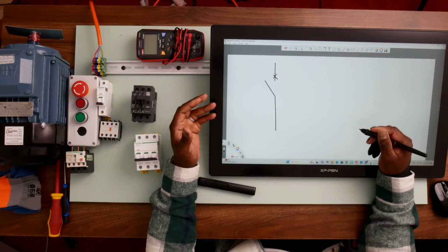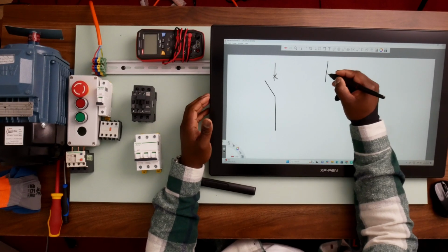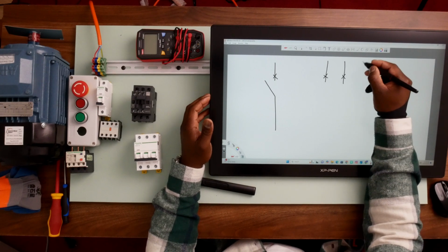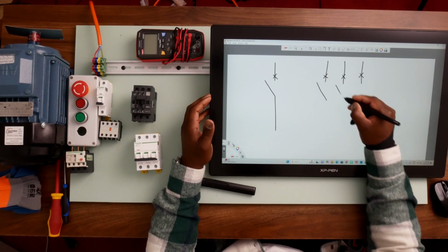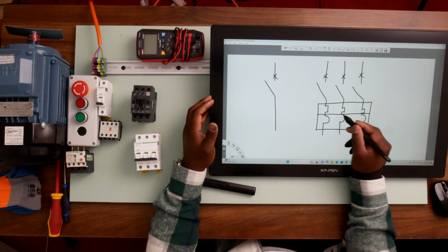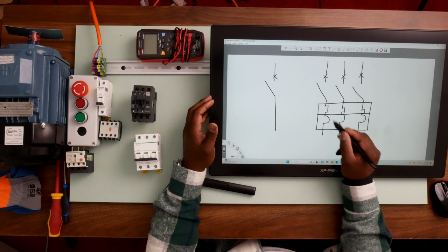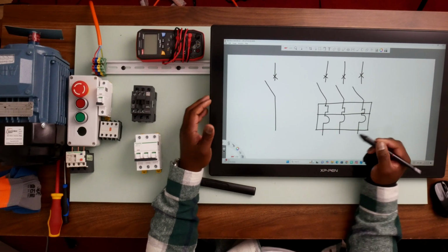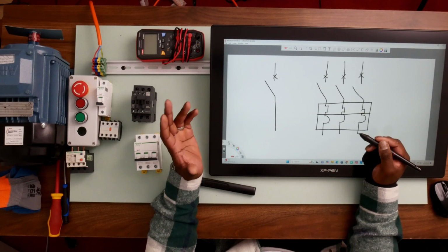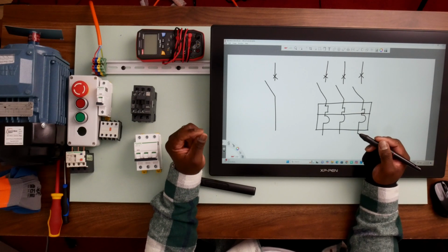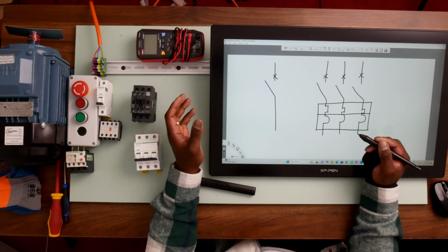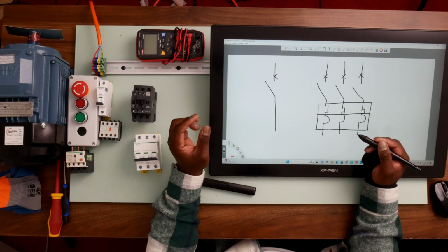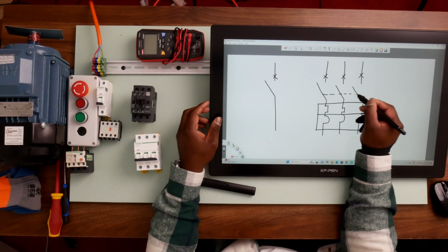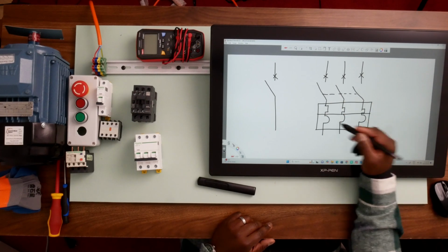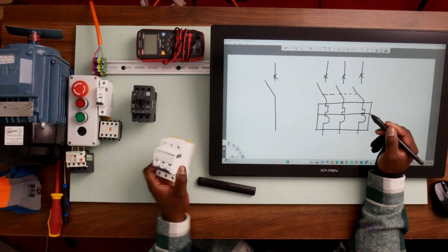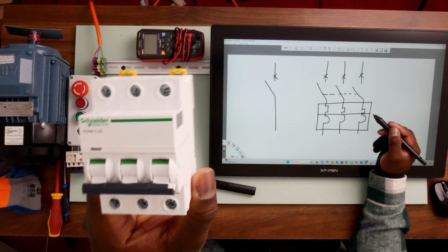But if you want to add more detail, you can draw this symbol here. And this is what you are more likely to come across in schematics. So this part here indicates thermal protection, and this part with these curves indicates magnetic protection. So a general circuit breaker normally has thermal protection and magnetic protection. But in a motor control circuit, we are installing those circuit breakers mainly for the purpose of protecting electric motors against short circuits. And we put a dotted line here on all the 3 poles. This just tells you that these 3 poles are mechanically linked, just like on this circuit breaker here.